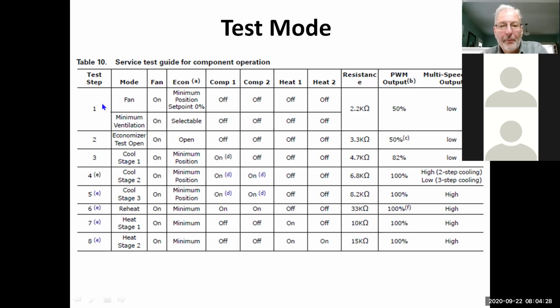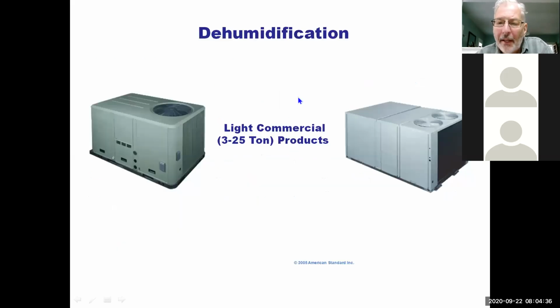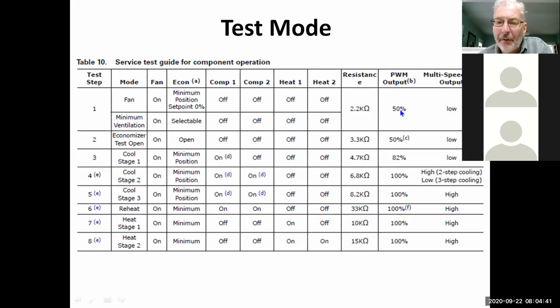But with some of the new units, and this will come into play when we're talking about fan setup, when you put these units in test mode, what happens on a lot of these new units is they only go to 50% airflow, okay? Economizer, they go to 50% airflow. Cool stage 1, they go to 82% airflow. So if you're trying to get something set up for test and balance, don't just throw it into a test fan or even a G signal, because you're not going to get full airflow. Some of the newer units have different airflows based on what we're doing here. So again, those are the different test options.